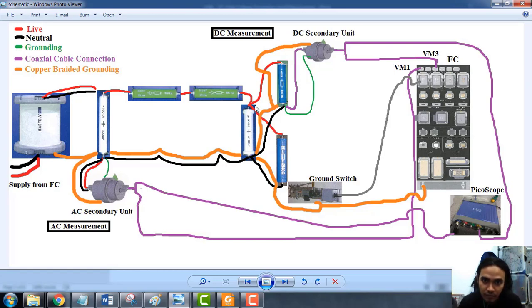From here we separate into two, connecting them in parallel. One connects to the parallel resistor, and from the parallel resistor we connect to the grounding switch using a cable, which connects to the grounding switch at the side cabinet of the frequency converter, for the DC measurement.